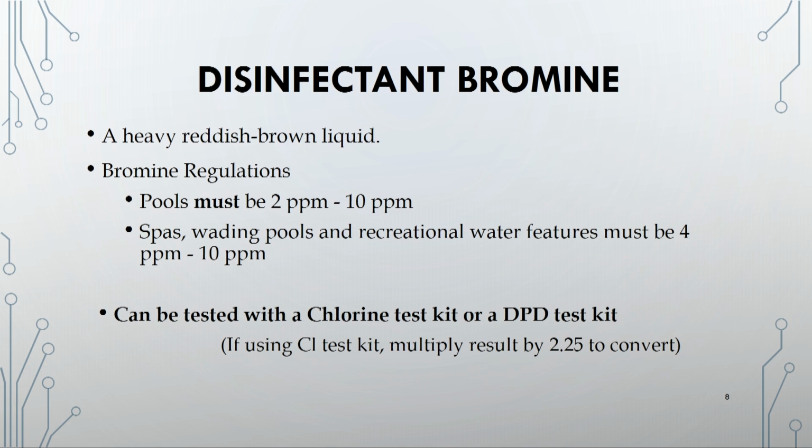Some pool operators enjoy the reduced effect of disinfectant byproducts, including bromamines, in indoor pools that use chlorine, because they may find it necessary to frequently shock the pool to reduce the chloramine levels, which can foul the air and cause corrosion to metal items around the pool, which is why they sometimes use bromine as well. Bromine is also known to have a less potent smell than chlorine, even when bromine is combined with ammonia or nitrogen. Combined bromine or bromamines also remain a viable sanitizer.